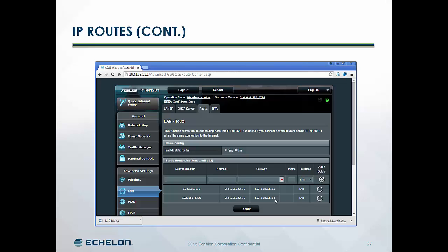If the LonTalk IP address was in a different subnet to the host IP address, we may also have a route from the LonTalk IP address of our IzoT router to its host IP address. But that's if they're on different subnets. In this particular instance, that's not the case.